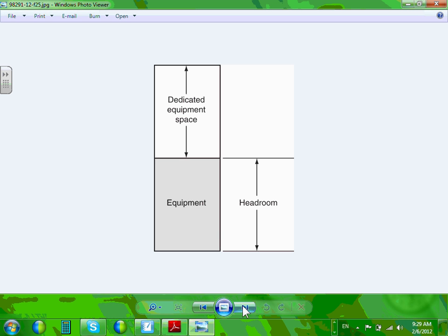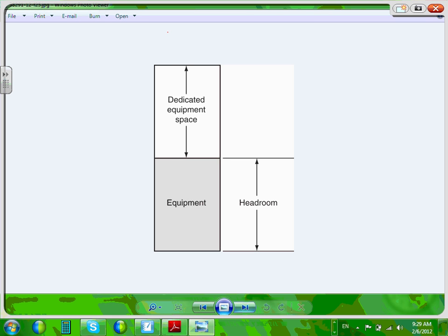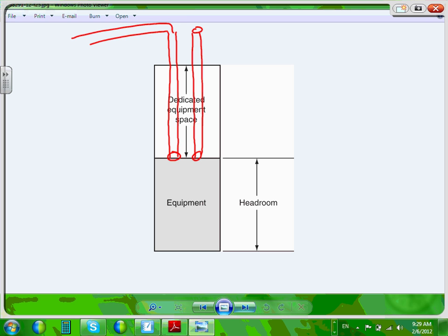Okay, now we move into something called dedicated space. By the way, that's it about the working space. We move into the dedicated space. The dedicated space is the space for the conduits. You guys remember what we talked about, space for the conduit? In order for you to bring your conduit right into the switchgear here, you want to bring your conduit almost always from the top or the bottom. Here's my conduit going this way. My conduit bringing power going this way, right?